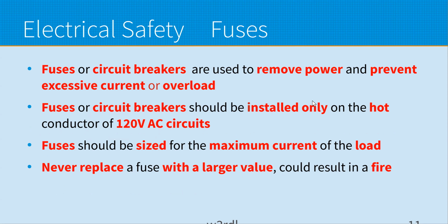Okay, fuses and circuit breakers. Their purpose is to remove power to try to prevent excessive current. The circuit breakers and fuses are both set to, in essence, trip or open at a specific current. Now, neither of them operates very fast. A fuse is probably faster than a circuit breaker. So you can still have some currents that exceed the rating on your circuit breaker or fuse for a short period of time. But at least they will stop continued excessive current where you could actually get enough heating or overload to cause a fire. So that's really the purpose.